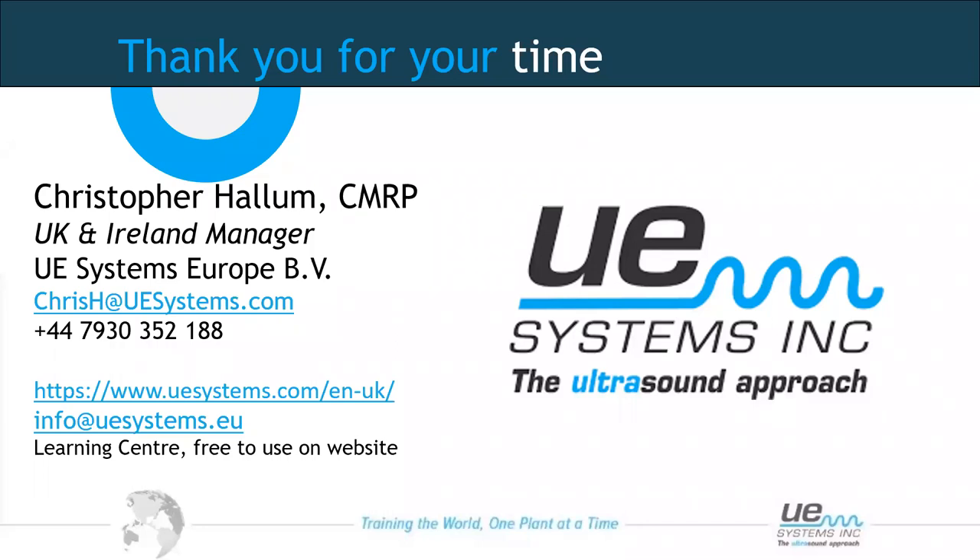On using ultrasound for steam traps: yes, we listen for turbulence on the outlet of the trap — we can listen on the outlet and hear the trap cycling up and down quite easily. The software with sound recordings checks for the amount of energy produced. If we see an increase in energy due to a lack of lubrication, we'll get a higher decibel value. If we see regular impacting, the FFT may show harmonics relative to the actual failure mode of that bearing.